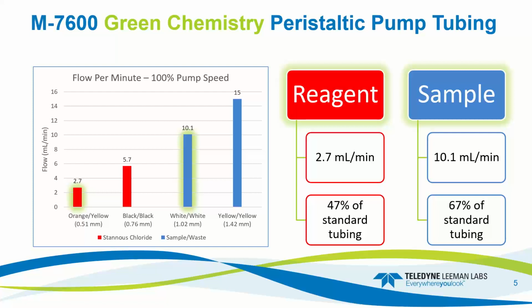So this graph compares the flow rate at 100% pump speed for both tubing configurations. The green tubing setup is kind of glowing green on the bars. For the green chemistry tubing, the stannous chloride reagent flow is 2.7 milliliters per minute, which is about 47% of the standard tubing flow. And the sample flow is 10.1 milliliters per minute, or about 67% of the standard tubing flow. So you can see that while the flows were reduced overall, they maintained a similar ratio between the tubing sets.